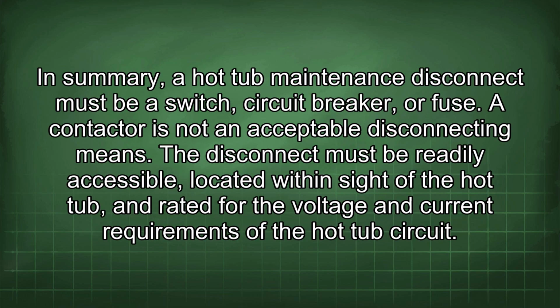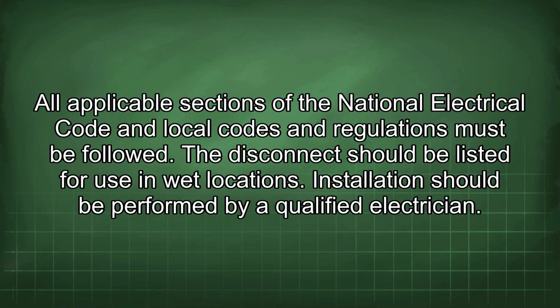In summary, a hot tub maintenance disconnect must be a switch, circuit breaker, or fuse. A contactor is not an acceptable disconnecting means. The disconnect must be readily accessible, located within sight of the hot tub, and rated for the voltage and current requirements of the hot tub circuit. All applicable sections of the National Electrical Code and local codes and regulations must be followed. The disconnect should be listed for use in wet locations. Installation should be performed by a qualified electrician.